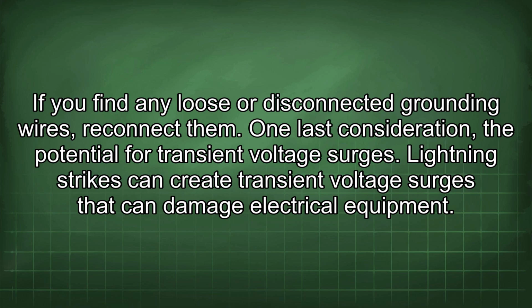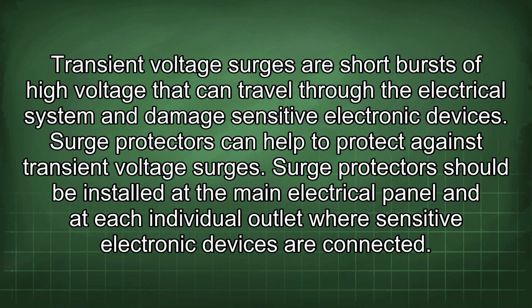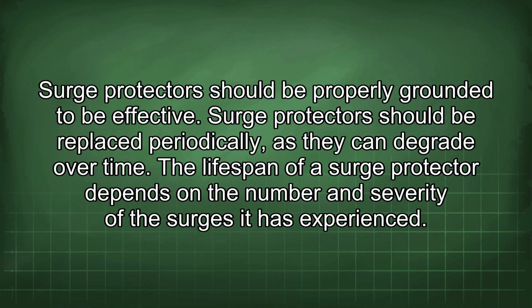One last consideration: the potential for transient voltage surges. Lightning strikes can create transient voltage surges that can damage electrical equipment. Transient voltage surges are short bursts of high voltage that can travel through the electrical system and damage sensitive electronic devices. Surge protectors can help to protect against transient voltage surges. Surge protectors should be installed at the main electrical panel and at each individual outlet where sensitive electronic devices are connected. Surge protectors should be properly grounded to be effective.